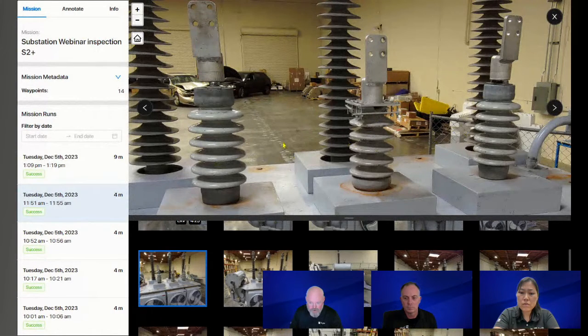That same mission can be flown. You can build missions for different differential schemes inside your station. If you've got multiple power transformers, you can build a flight plan for each one. In case there's a differential, you can get out there and inspect that transformer quickly and determine if it's a wildlife incident or some other type of failure that's going to require a larger crew.